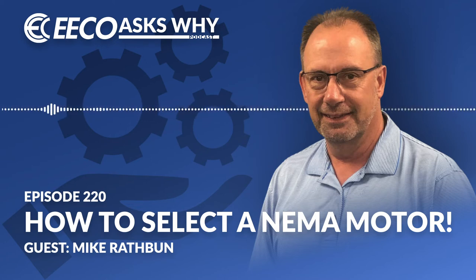Another aspect I want to touch on that I think gets missed quite a bit, especially when we see RFQs come through where people are replacing existing motors, is the NEMA design designation. There's basically four designations for NEMA design, and that's design A, B, C, and D. What they really speak to is the design of that motor and its capability to apply a general or a specific torque curve depending on what type of load you have.